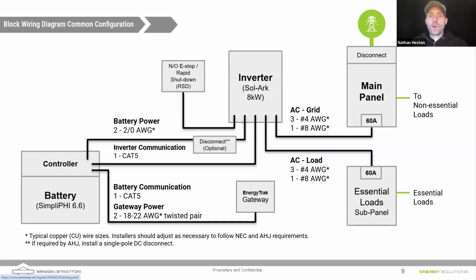So a wiring diagram for a smaller inverter like the 8K or the 12K might look something like this. So you'd be feeding that. Notice we're feeding that out of the main load panel with a 60 amp breaker, Daniel. Would a 200 amp panel allow you to backfeed 60 amps of solar? How can we do that? Well, one, you could derate the main to limit the amount of incoming current from the grid. You could theoretically have a 225 bus bar that would allow that.